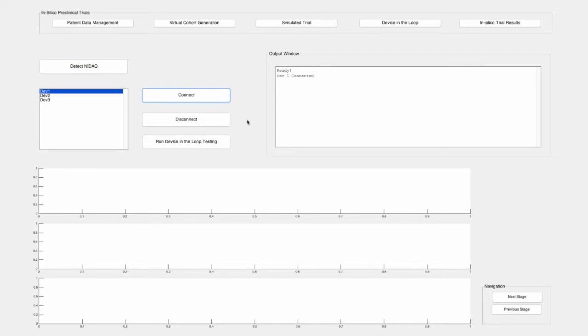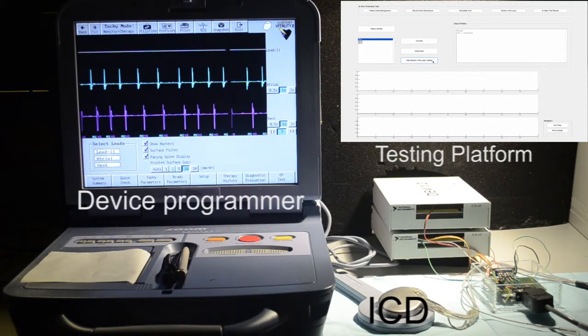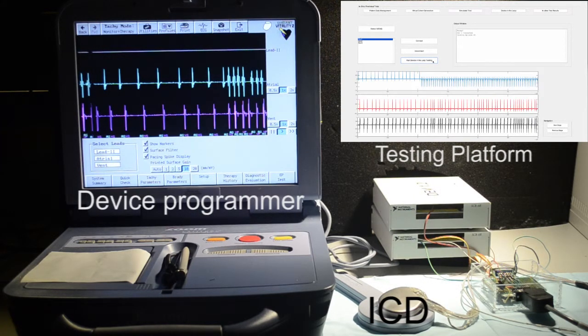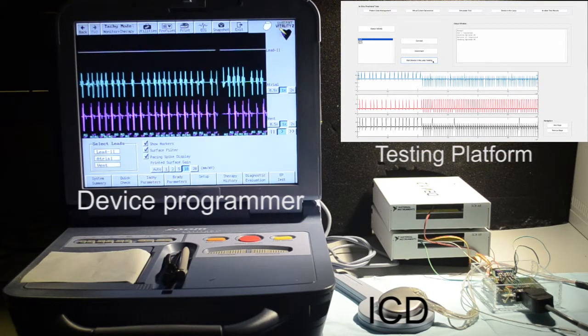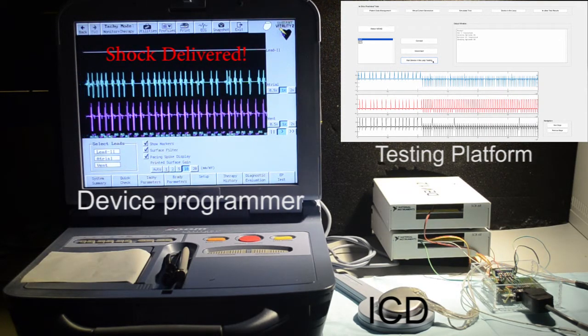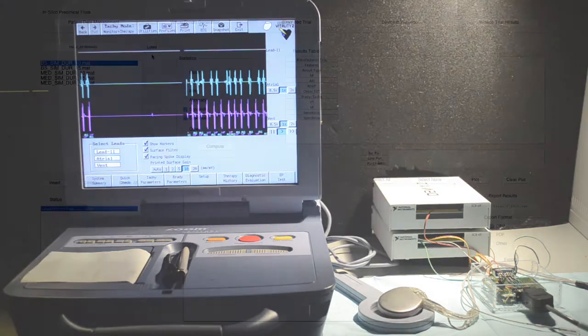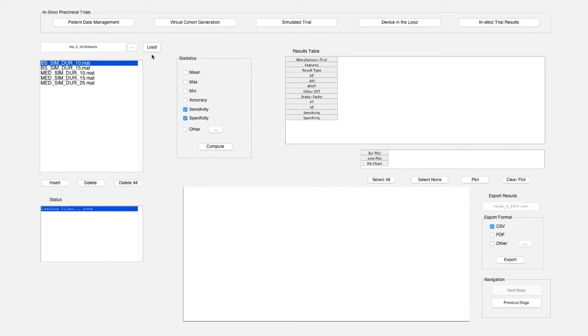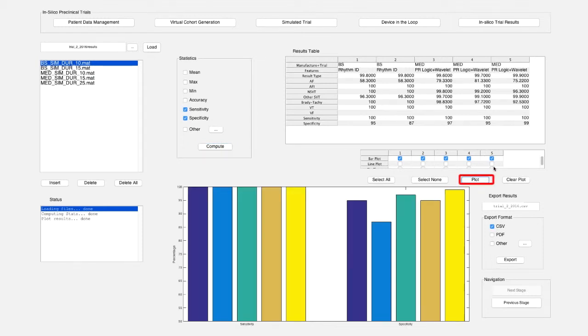The synthetic signals are then fed to the real device through a data acquisition system, which can report whether a shock event occurs. You can observe the signals fed to the device through the toolchain on the device programmer. Now a shock therapy has been delivered and successfully acquired. The results of the in-silico trials from simulation and device-in-the-loop testing are viewed in the final step of the toolchain. Statistics, such as device sensitivity and specificity, are summarized and displayed as a table and a graph.